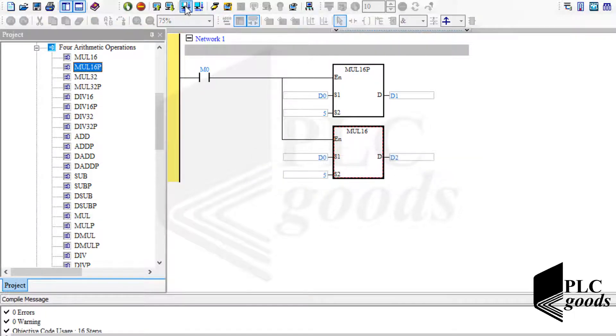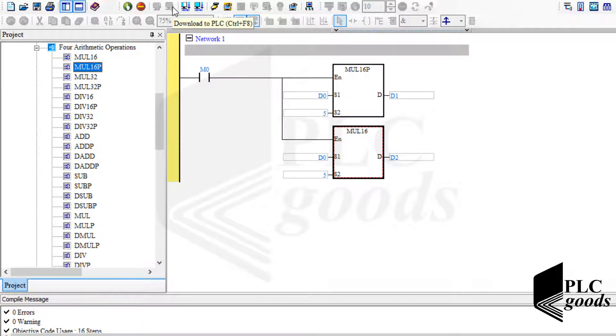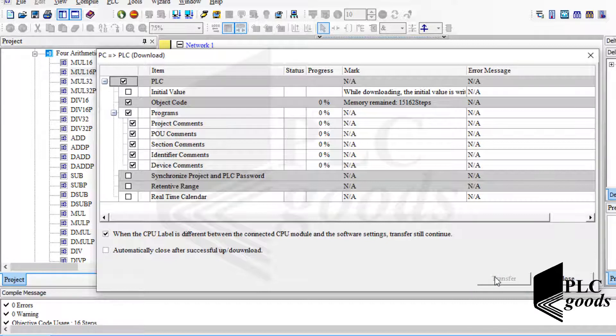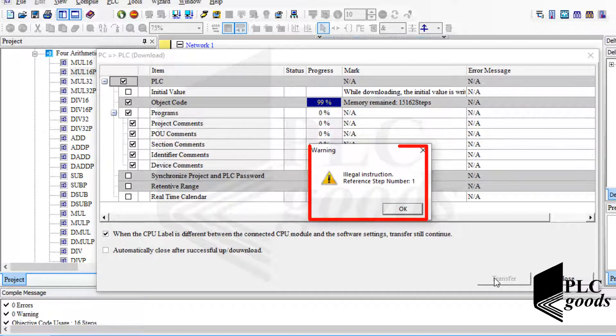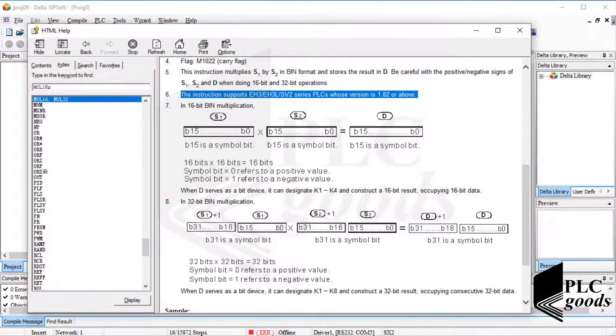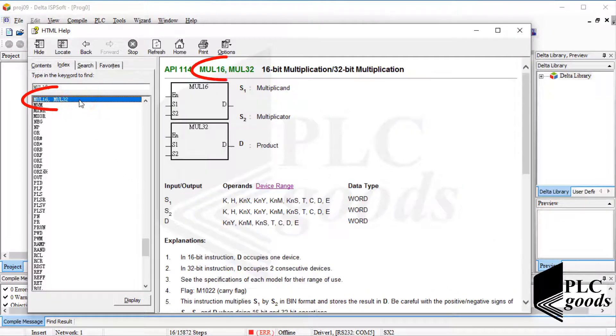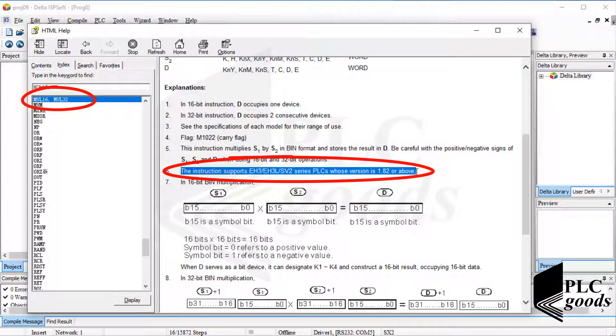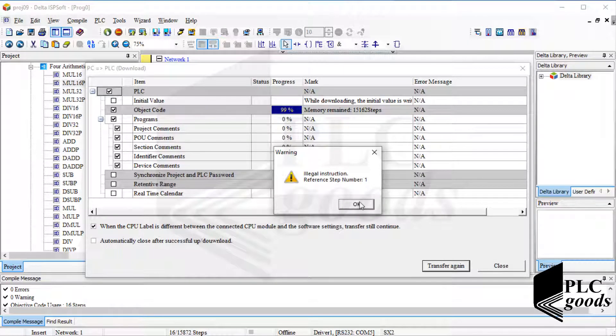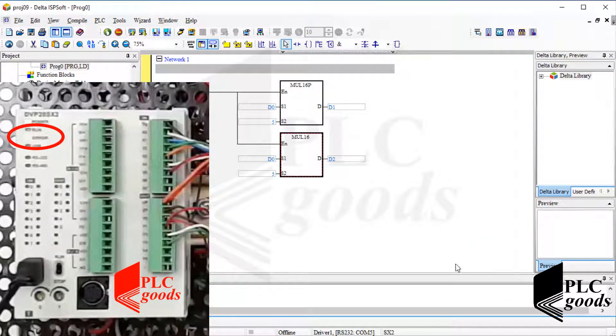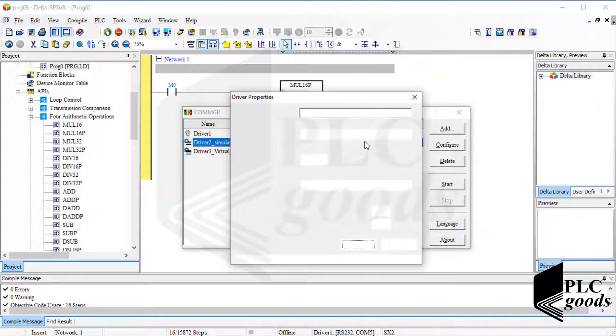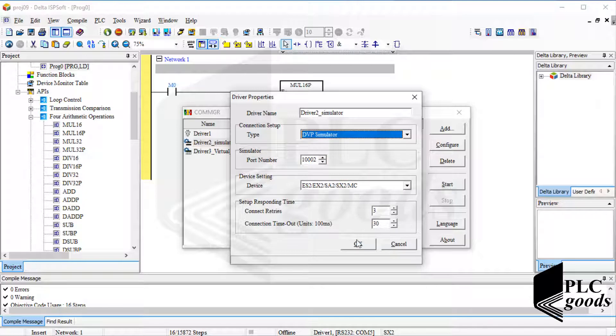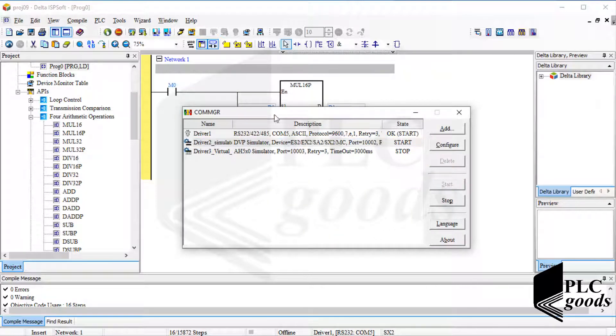Now let's compile the program. There isn't any error or warning. Now let me download the program. Pay attention - this warning message says I'm using an illegal instruction. Note that based on the selected PLC series, ISP Soft displays instructions which are valid, but maybe some instructions are not supported by some versions. My PLC doesn't support the used multiply instructions, and as you can see the error LED has been turned on. So let me continue this video with the Delta simulator. First I must use COM MGR software to activate the simulator, and then change communication settings inside ISP Soft.